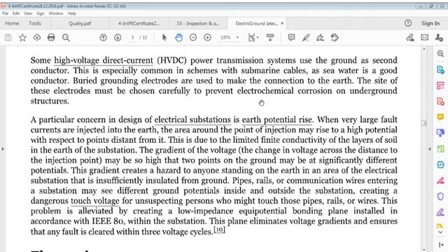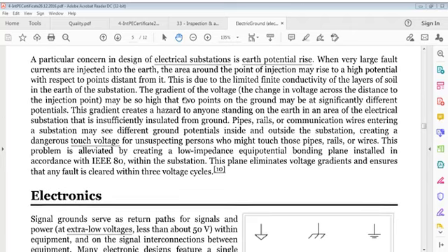So I read again. Some HVDC power transmission systems use ground as a second conductor. This is especially common in schemes with submarine cables, as seawater is a good conductor. Buried grounding electrodes are used to make connection to earth. The site of these electrodes must be chosen carefully to prevent electrochemical corrosion on underground structures. A particular concern in the design of electrical substations is earth potential rise.